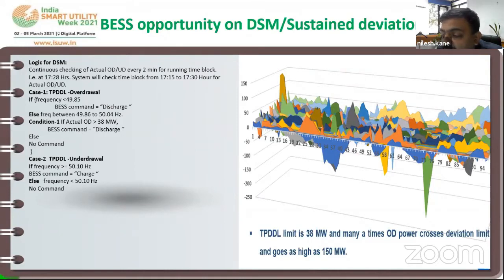To take care of that, we have an automatic logic of DSM, the deviation settlement mechanism, in which we monitor every 5 minutes the underdrawal and overdrawal. A typical example has been given, and we try to operate as a power utility in a band of 49.85 to 50.05. Every 2 minutes we monitor the underdrawal and overdrawal, and appropriately the battery's discharge and charging decisions are taken. This can operate manually as well as automatically, and it is integrated with our SCADA.